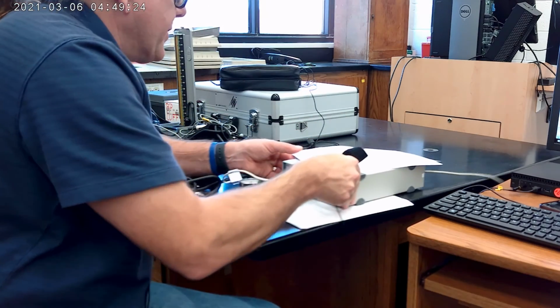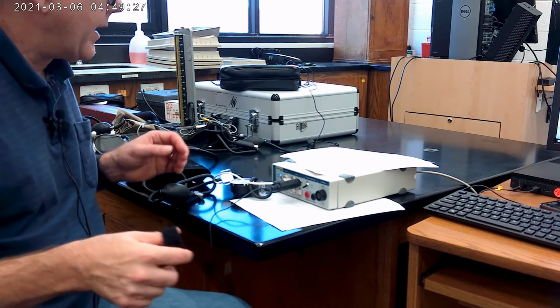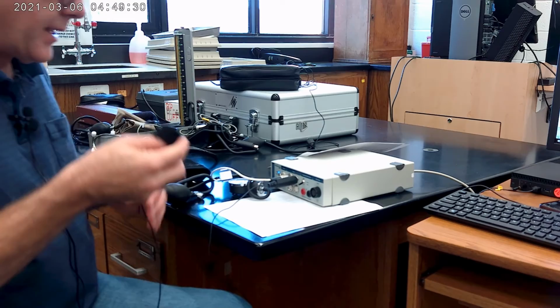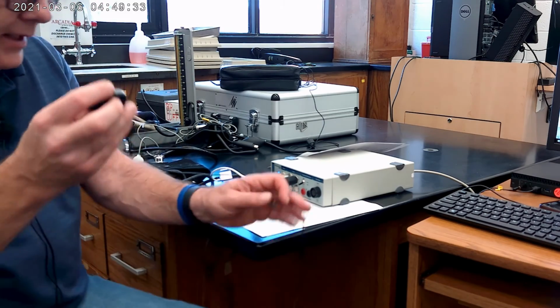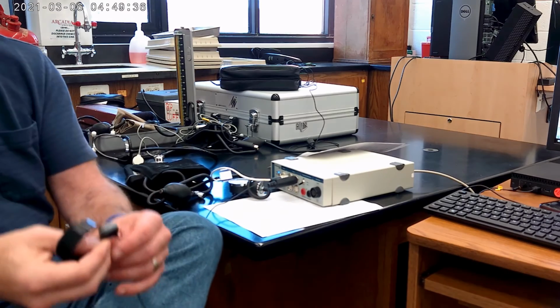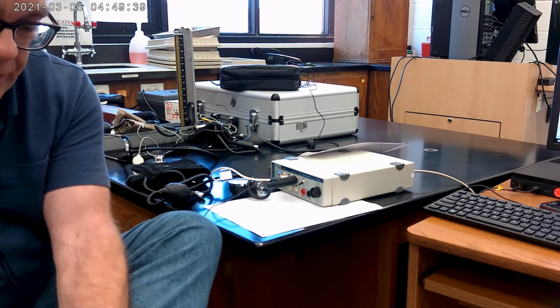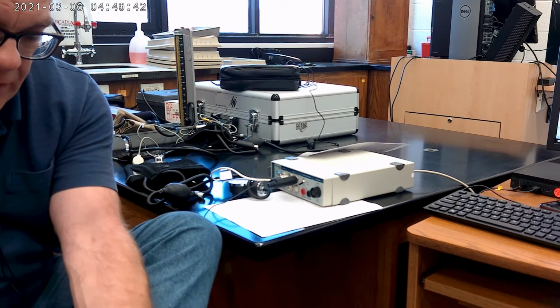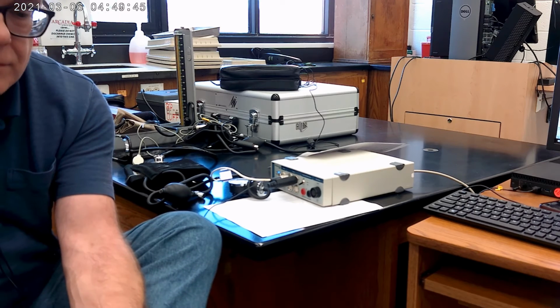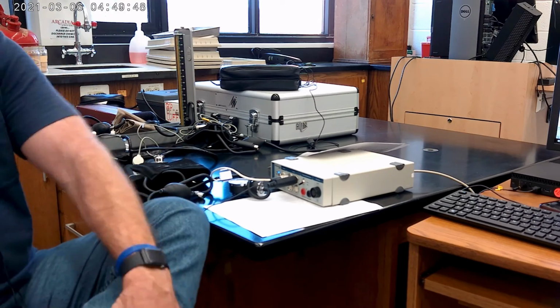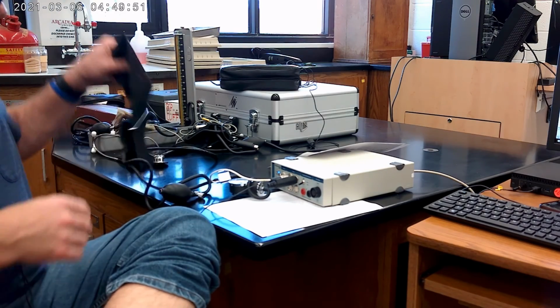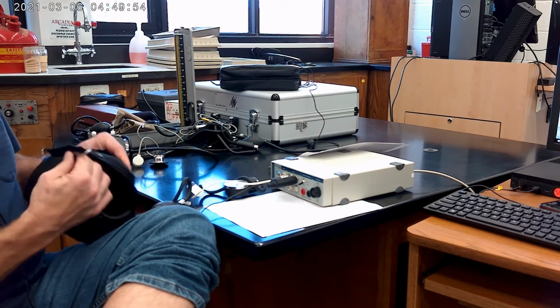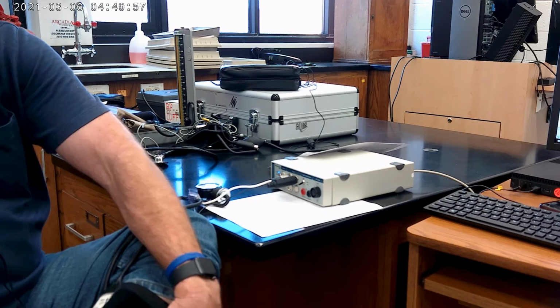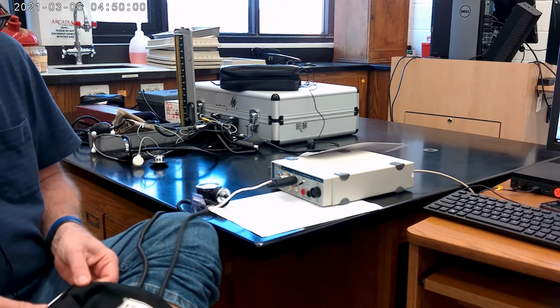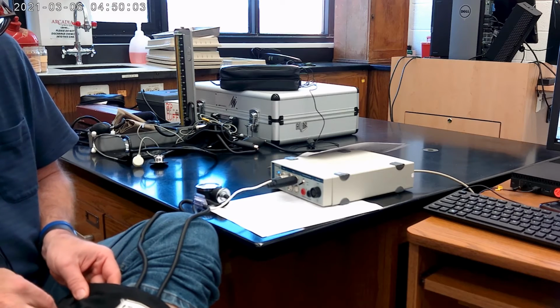And our pulse transducer is a little bit short, so we may have to position this on the floor. I think we're okay right now. What we're going to want to do is take our finger pulse transducer and put it on our left big toe. Now keep in mind, you don't want to step on the pulse transducer. You don't want to do damage to that. And so we're going to put it on my left toe. And we're going to put the blood pressure cuff on before the pulse transducer. We're going to put the blood pressure cuff on the calf of my left leg.